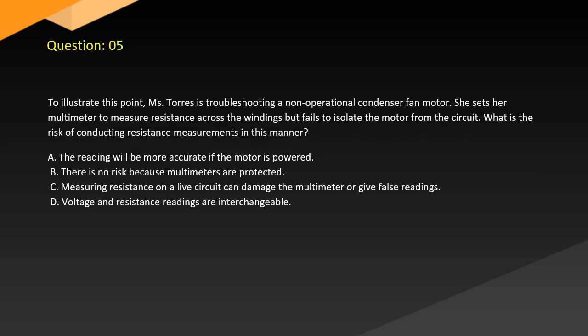Question 5. To illustrate this point, Ms. Torres is troubleshooting a non-operational condenser fan motor. She sets her multimeter to measure resistance across the windings but fails to isolate the motor from the circuit. What is the risk of conducting resistance measurements in this manner? A. The reading will be more accurate if the motor is powered. B. There is no risk because multimeters are protected. C. Measuring resistance on a live circuit can damage the multimeter or give false readings. D. Voltage and resistance readings are interchangeable.